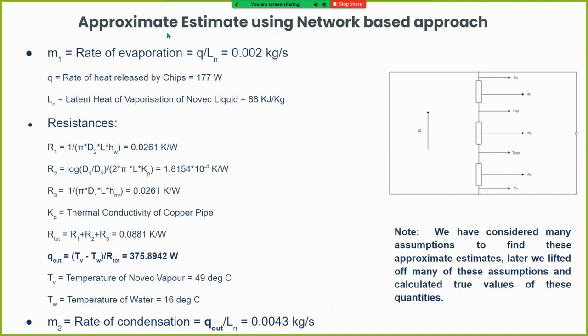We performed an approximate estimate using a network-based approach with several simplifying assumptions, verifying the neglected heat transfer processes afterward. The thermal resistance network includes R1 — convection from the inner surface of the pipe to the coolant water; R2 — conduction between the outer and inner surfaces of the pipe; and R3 — convection from Novec vapor to the outer surface of the pipe. Using this network, we found the rate of evaporation, rate of condensation, and the heat Q_out that we are able to extract.